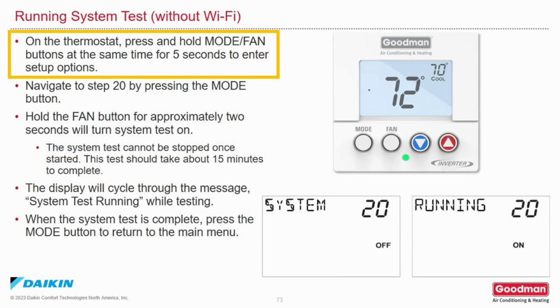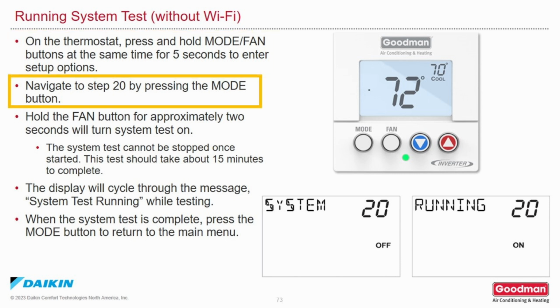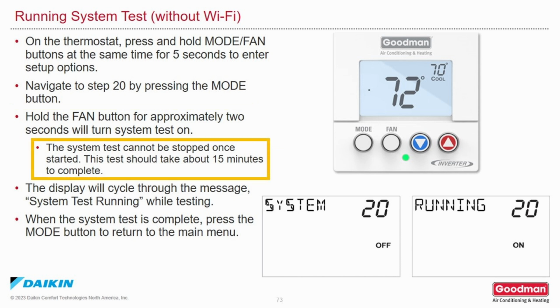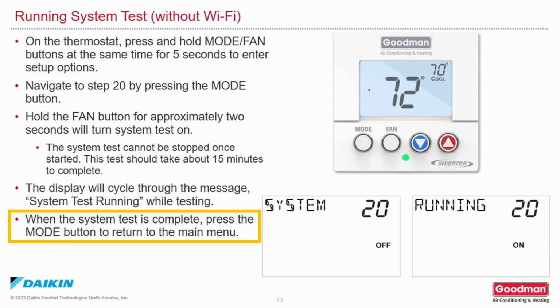On the thermostat, press and hold the mode and fan buttons at the same time for 5 seconds to enter setup options. Scroll down to step 20 by pressing the mode button. Holding the fan button for approximately 2 seconds will turn system test on. System test cannot be stopped once it's started. This test should take about 15 minutes to complete. The display will cycle through the message, System Test Running while testing. When the system test is complete, press the mode button to return to the main menu.